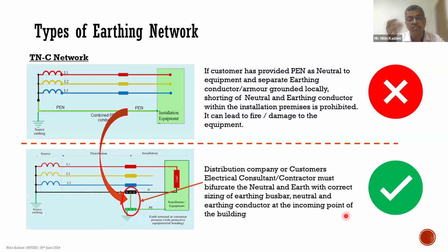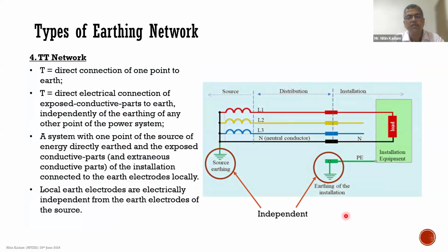Now, there are also certain questions which come up: how can we distinguish between the TNC network and the TT network? But before we talk about that, we'll go to the next slide and see what the TT network is. In the case of a TT network, there are 4 wires again coming to the installation: 3 phases, and a neutral which is coming from the star point of the transformer secondary. And there is no direct connection between the source earthing and the earthing of the installation. They are both independent and not connected directly. And this type of network is called a TT network.